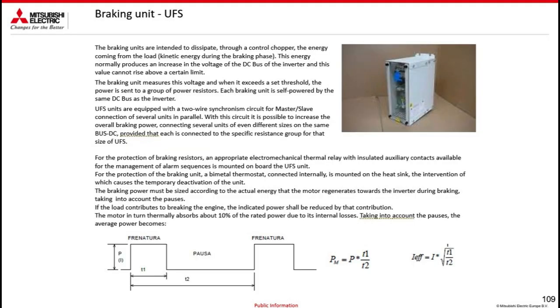In the models above 55 kilowatts, there is the possibility of installing an external braking unit. This external braking unit is very useful because it allows you to dissipate 100% of the energy of the nominal power, whereas the FRD and FRE 700 could reach a maximum of 30% continuous as dissipation power, while with the unit you can reach 100%. The FRF 800 and the FRE 800 on board already allow you to dissipate 100% by default. The external unit, which will also be equipped with a braking resistance, is wired directly to the DC bus, so between P and N.